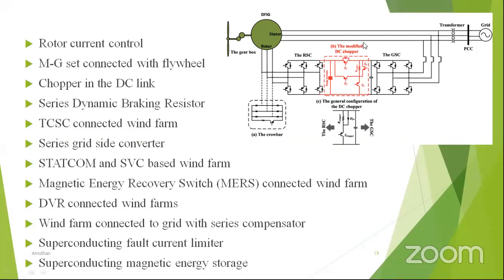Given how the chopper is connected in the DC link to improve the voltage sag ride-through problems, a slightly modified chopper is included in this DC link of back-to-back converters, and that performance they study. Okay, and there are some more things also available, like series dynamic braking resistor and TCSC connected wind farms and series grid side converters.